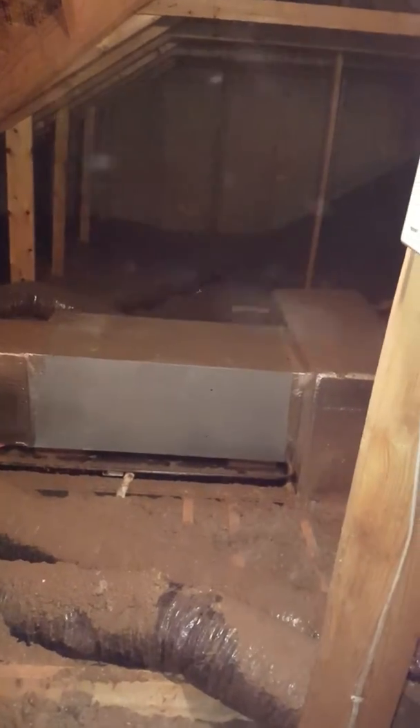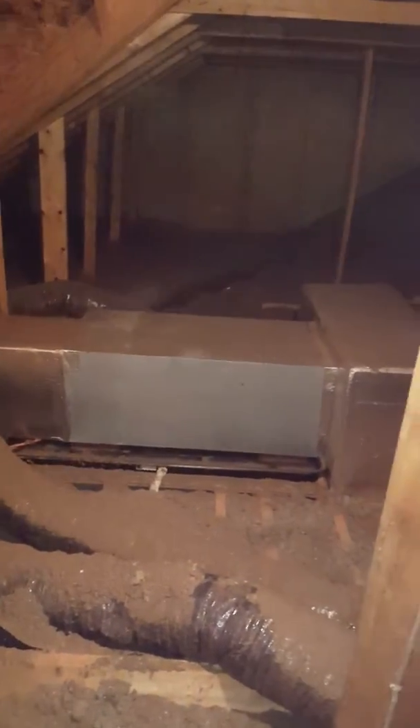Here at Carl Booth Residence, looking at a two and a half ton air handler with the two and a half ton heat pump outside. The line set is three-eighths, three-quarter, and it's on the other side of the unit.